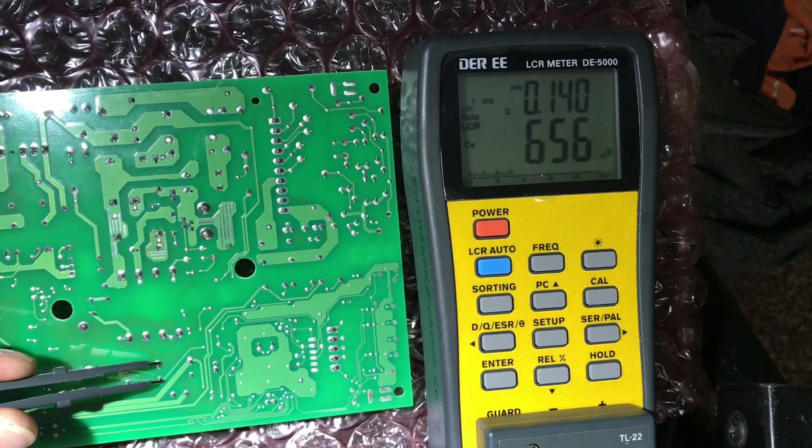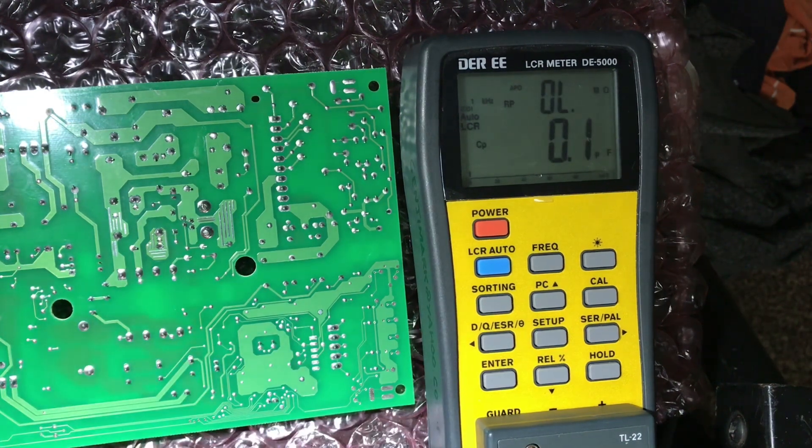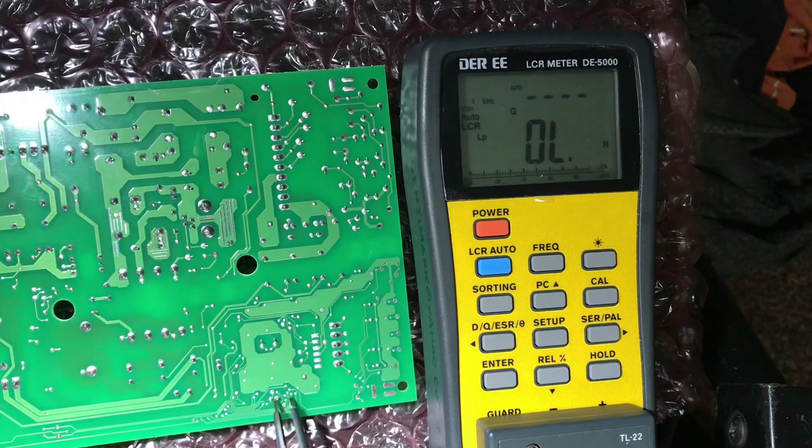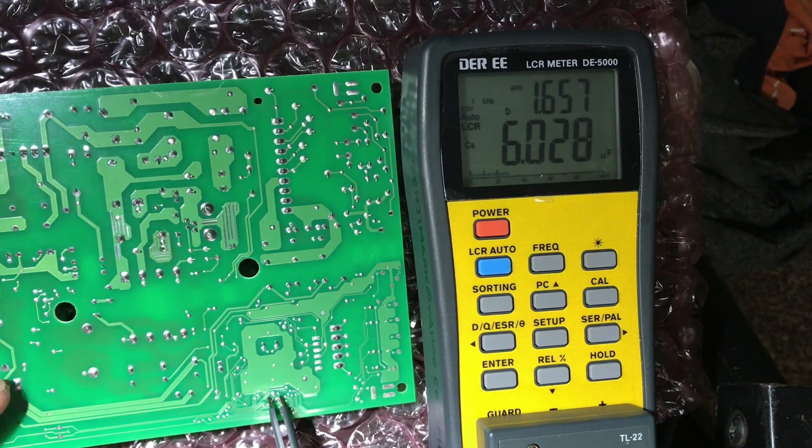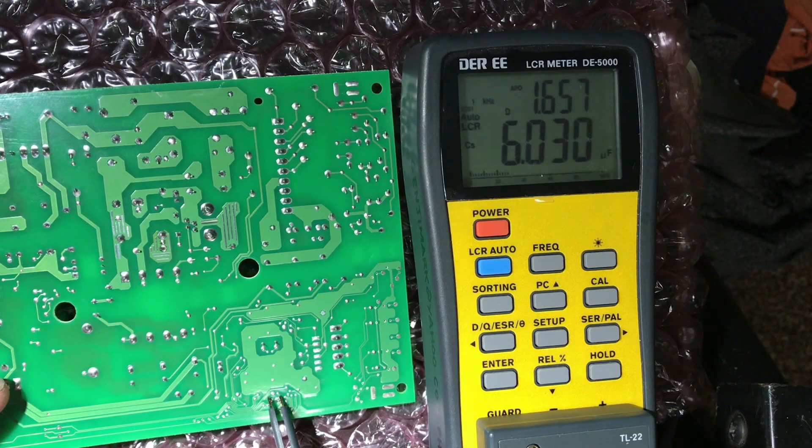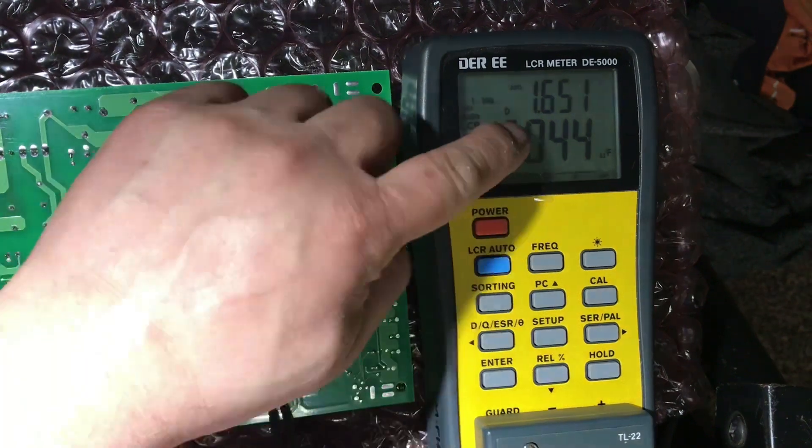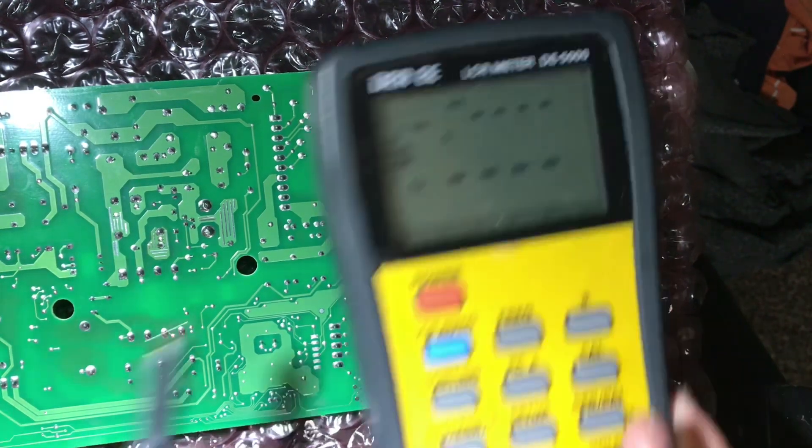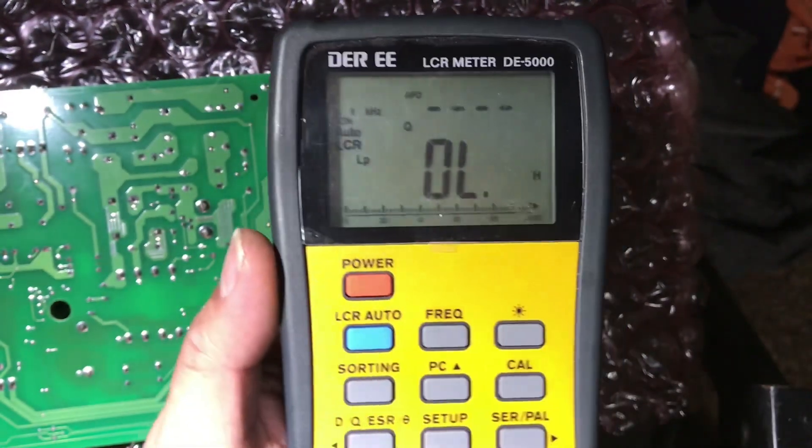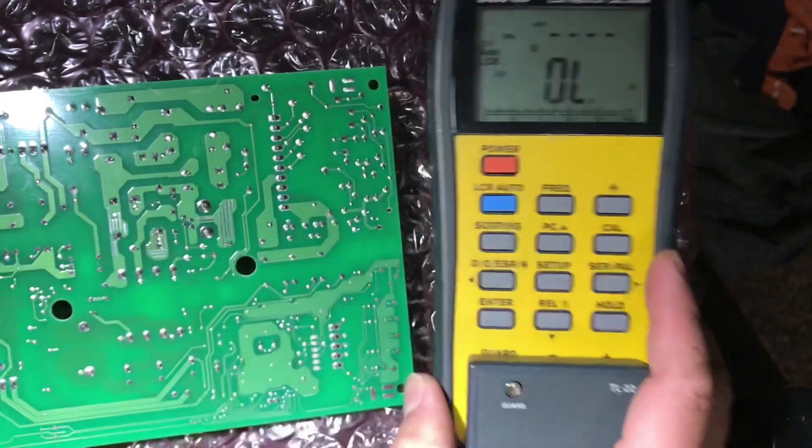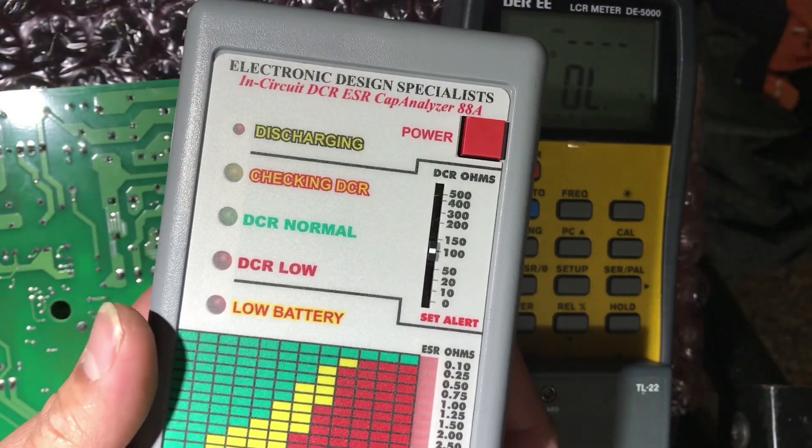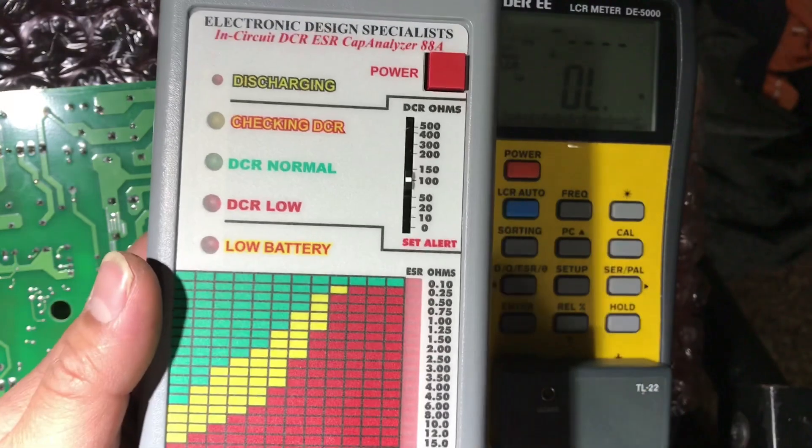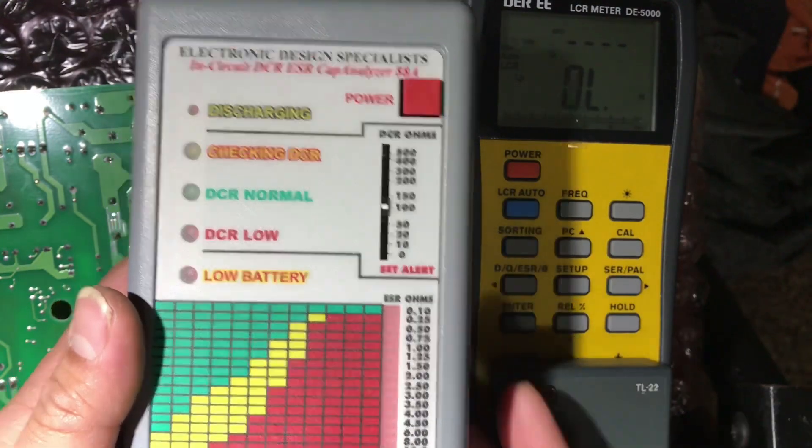This tells me that these three capacitors are good, and this one here tells me it's bad because of this dissipation factor value that it shows me on that screen there. That's the good thing with this meter - I like this. And it's not very expensive compared to this one here, which is very expensive but not much it can do. Very basic, simple - it can only test capacitor and resistor, that's all.